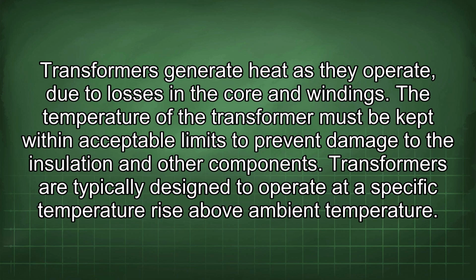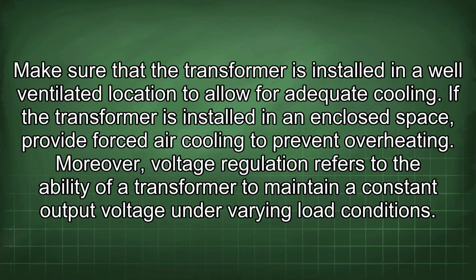Transformers are typically designed to operate at a specific temperature rise above ambient temperature. Make sure that the transformer is installed in a well-ventilated location to allow for adequate cooling. If the transformer is installed in an enclosed space, provide forced air cooling to prevent overheating.